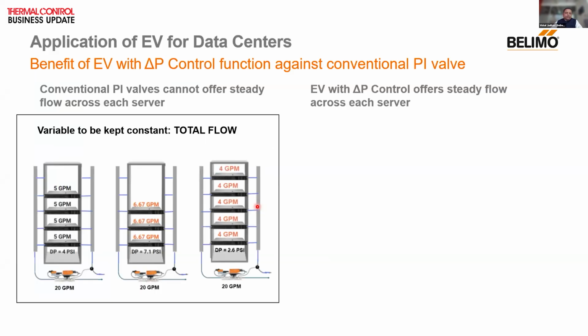Again, I will explain with detailed schematics. So let's say this has 20 GPM as a supply, and this operates on the temperature difference. It will keep on pumping 20 GPM, but your differential pressure will change across the racks. So for example, in this case, delta P is 4 PSI. At that combination, you have 20 GPM being supplied.